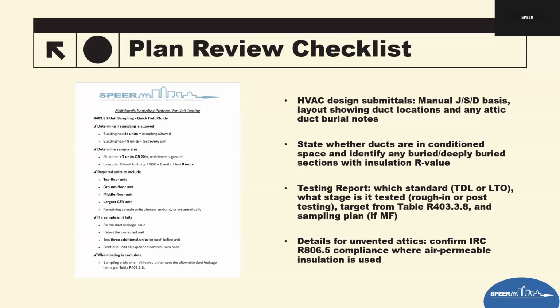The duct layout is also especially important. It should show the duct location, size, returns, and any proposed attic duct burial details. If the ducts are going to be in a vented attic, reviewers should look for notes about R-values and buried ducts. Next, the plans must clearly state whether ducts are in conditioned space.